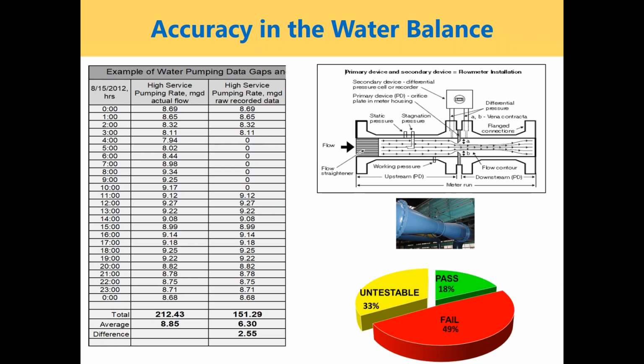I said all that to articulate the difference between testing and calibration. Testing looks at the hydraulic piece, the primary device, where the initial measurement occurs. Calibration pertains to the electronics or the signal coming off the secondary device. It's more of an electronic relationship: is it programmed correctly, is it spanned correctly, and if you have a SCADA system, does what's leaving step 2 show up the same at step 3?